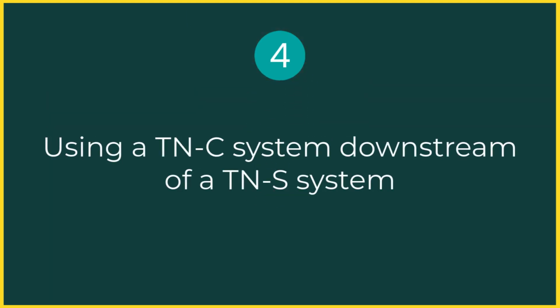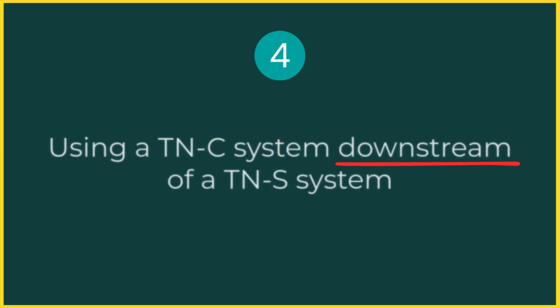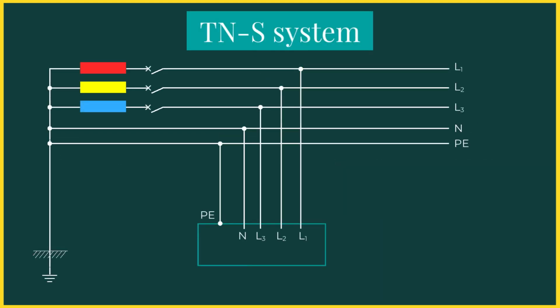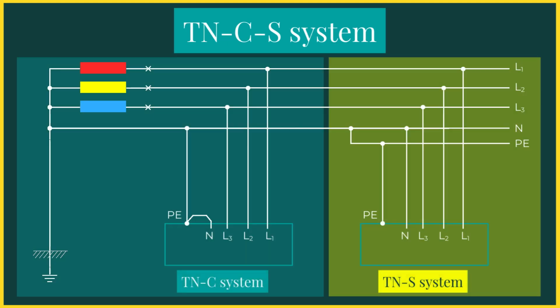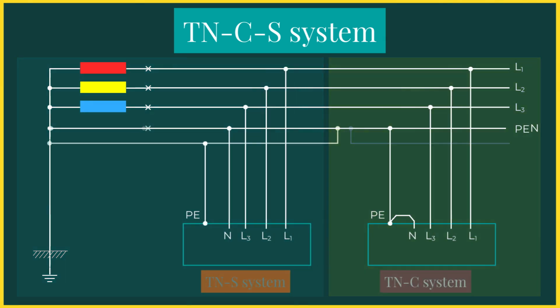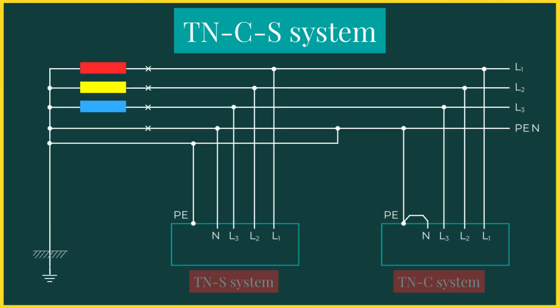Mistake 4. Using a TNC system downstream of a TNS system. The TNC and TNS systems can be used in the same installation. This arrangement is known as a TNCS system. However, a TNC system must never be used downstream of a TNS system. If the neutral conductor is accidentally interrupted in the upstream TNS section, the protective conductor in the downstream TNC section would also be interrupted. This would expose users to a serious danger.